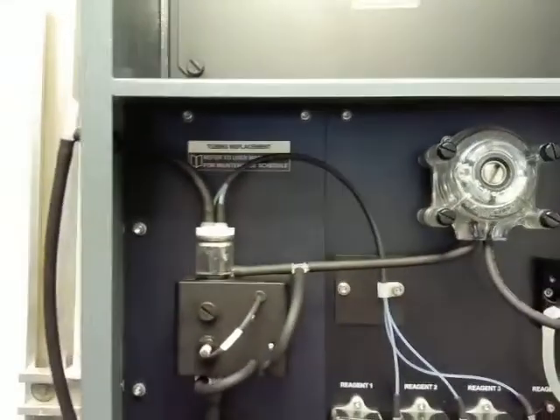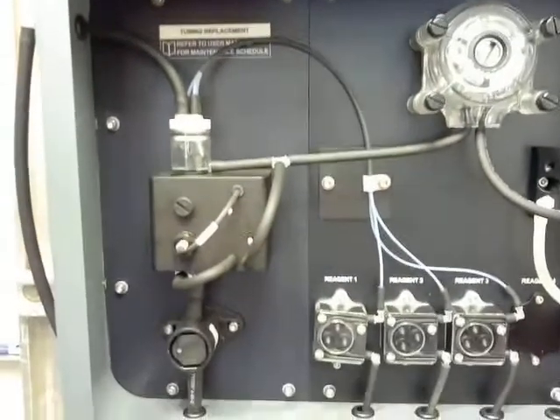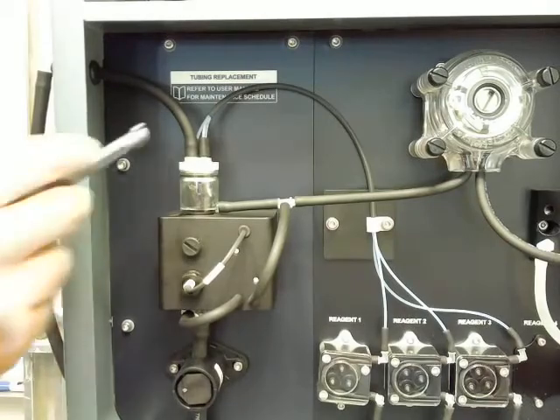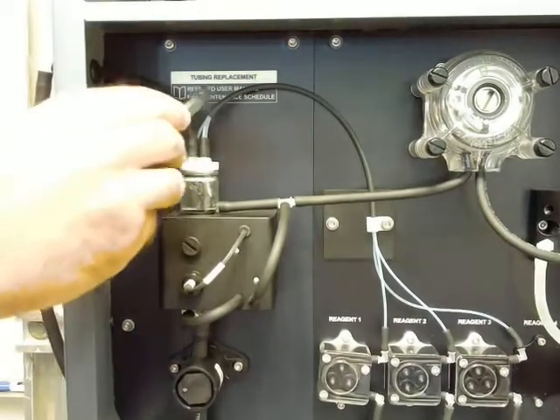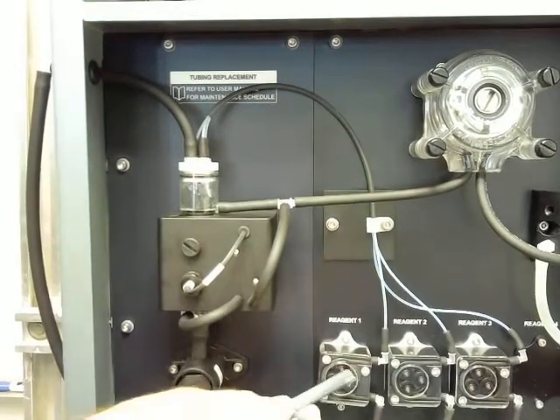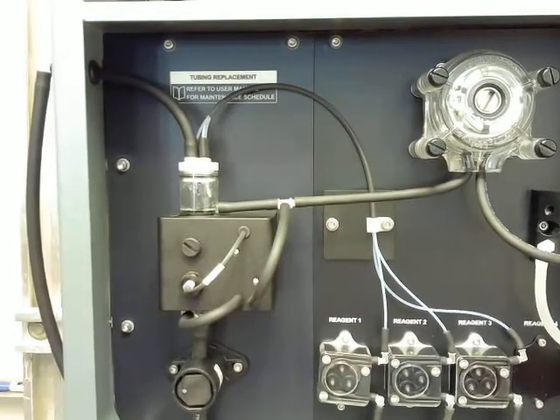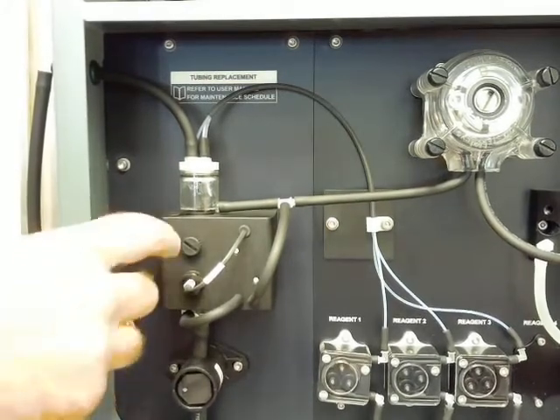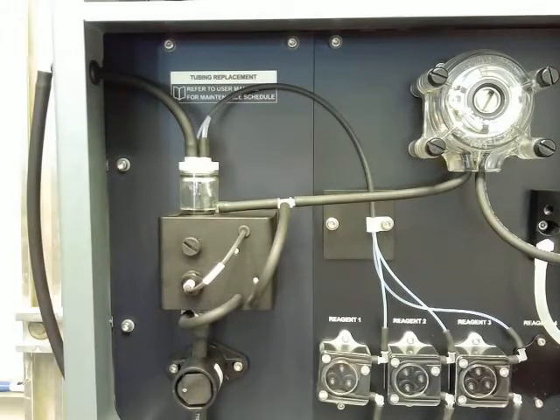And a little bit closer look at our flow cell block here. Cap right here, overflow tubing, reagent tubings down to our pumps. Copper will have all 3 of these pumps. The monochloramine will only have 2. This little screw here is just a thumb screw that holds the flow cell in place. And then here's our LED. At the end of this, I'll take this block off, and we'll see inside we have the mixing pump, the detector board on the back side, and there's also a small heater, which isn't super hot, so this block will just be a little bit warm to the touch. That just helps catalyze our reaction, make sure our reaction doesn't take too long, especially if our sample was a little bit on the cooler side.